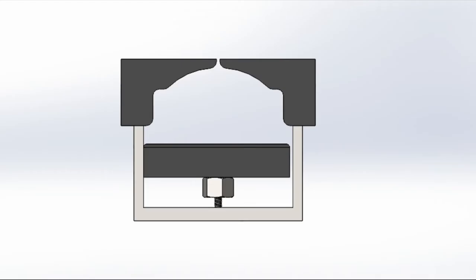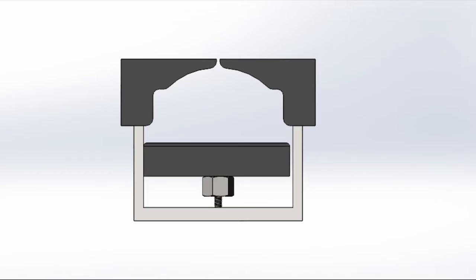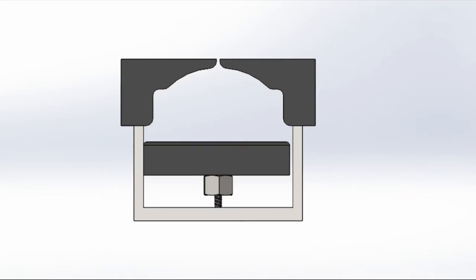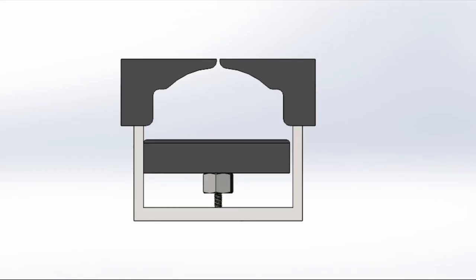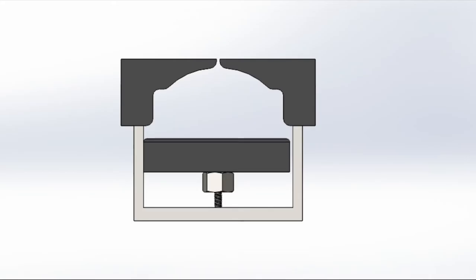The rubber pads for the palm will be mounted with a steel bracket that will go under the platform where the hand is resting. The center of the bracket will be bolted to a lead screw connected to a stepper motor. There will be a load cell bar between the lead screw and bracket to measure the proper force exerted by the motor so as not to hurt the client.